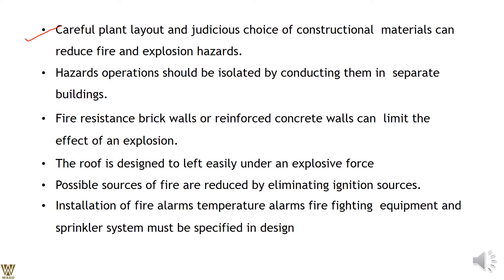Fire-resistant brick walls or reinforced concrete walls can limit the effect of an explosion. The roof is specially designed to lift easily under explosive forces. Possible sources of fires are reduced by eliminating ignition sources. Installation of fire alarms, temperature alarms, firefighting equipment, and sprinkler systems must be specified in the design.